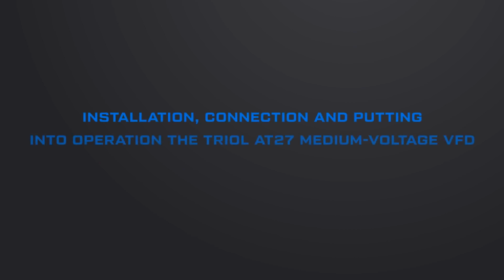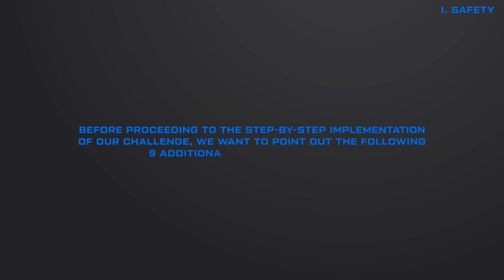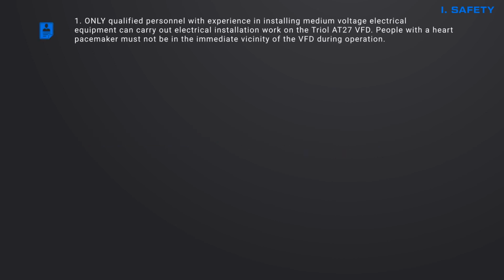In this tutorial, we will tell you how to quickly and reliably install, connect, and put into operation the Triol AT27 medium voltage VFD. Safety. Before proceeding to the step-by-step implementation of our challenge, we want to point out the following 9 additional security measures. The VFD is connected to hazardous voltages and operates machines with rotating mechanical parts that are sources of danger. For this reason, only qualified personnel with experience in installing medium voltage electrical equipment can carry out electrical installation work on the Triol AT27 VFD.